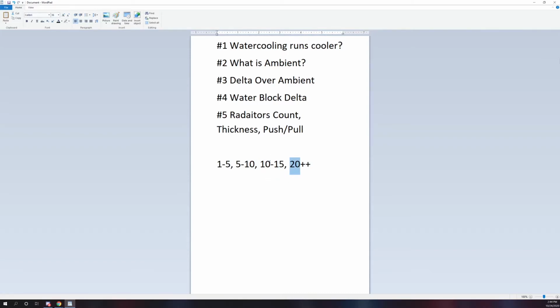So this is how you can tell if your temperatures are too high, right? So if you're sitting there and you're wondering if your loop is performing poorly and your water temperature is 50 degrees, but your room's only 24, then you have a problem. This is why I say a temp sensor is extremely important. And from there, you can troubleshoot. Maybe you have the in and out reversed. Maybe your pump died. If your pump died, your water temperature is going to go up real quick. Maybe your fans died, and that will slowly build up temperature in your loop. So you get the idea.